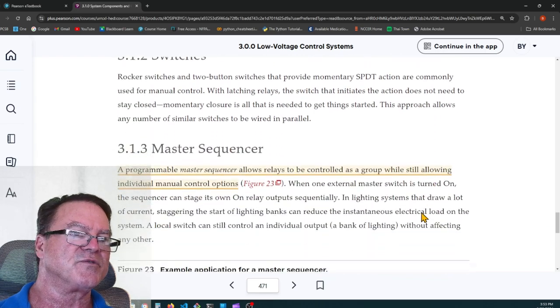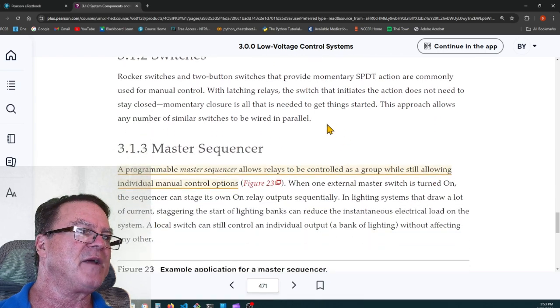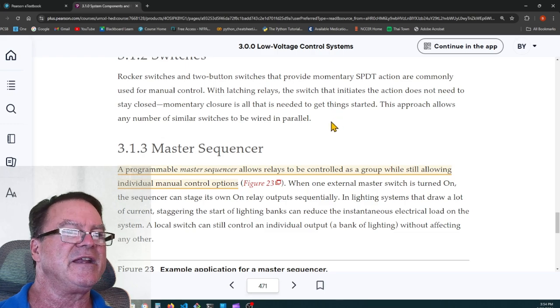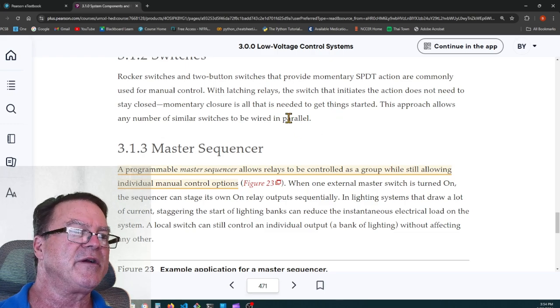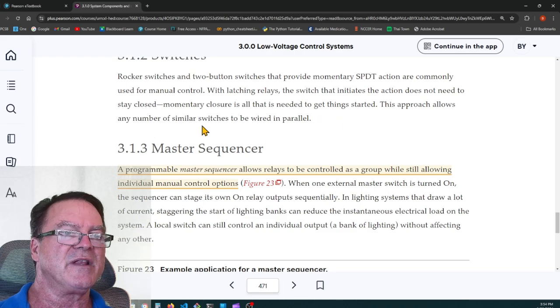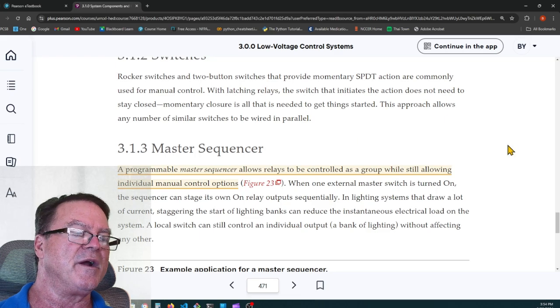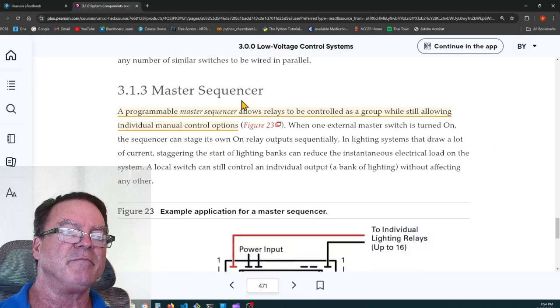Switches. Rocker switches and two-button switches that provide momentary single-pole double-throw action are commonly used for manual control. With latching relays, the switch that initiates the action does not need to stay closed. Momentary closure is all that is needed to get things started. This approach allows any number of similar switches to be wired in parallel. Here's a highlight, master sequencer.